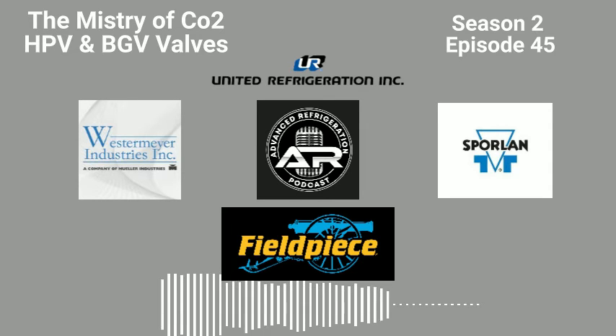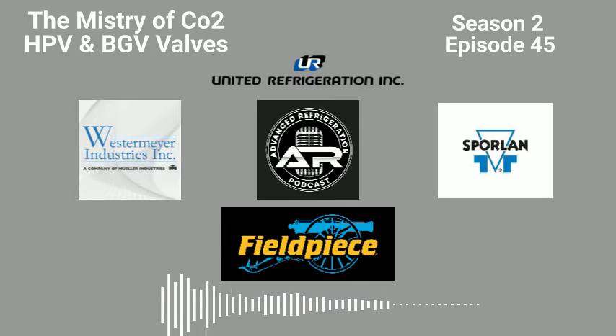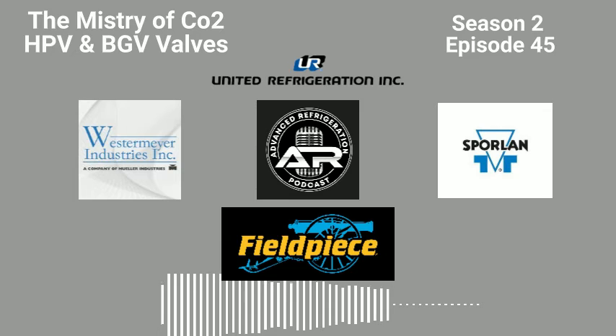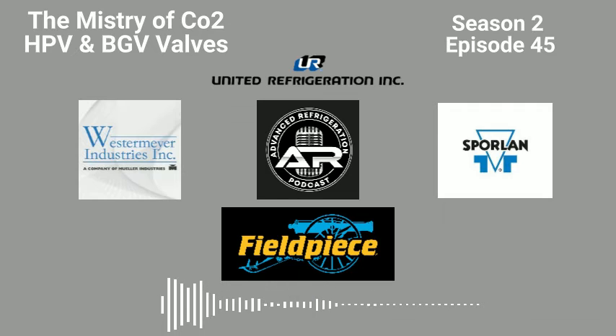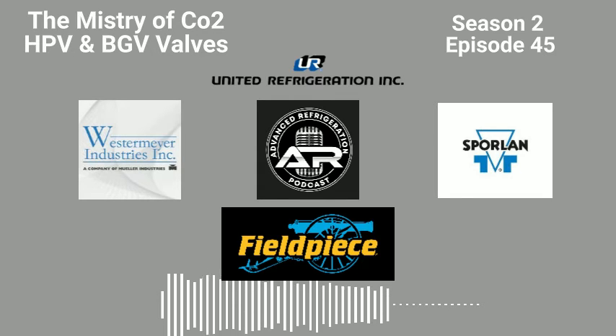Because, I mean, that's less load in the flash tank, because now your flash tank, your drop leg pressure is coming down to a minimum. Say you may only be running 650 pounds. Okay, so now it only has to drop 150 pounds. Say your pressure is 500 pounds and you're dropping 150 pounds. So that flash gas bypass valve may only be pulling 5% off the top of that receiver, flash tank. So go ahead, Brett.